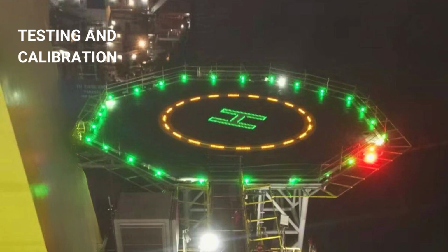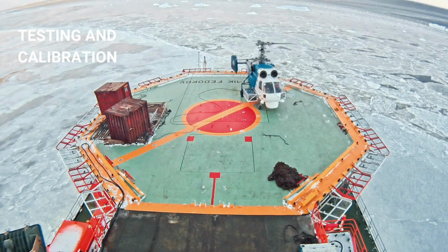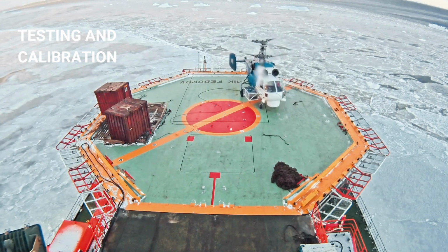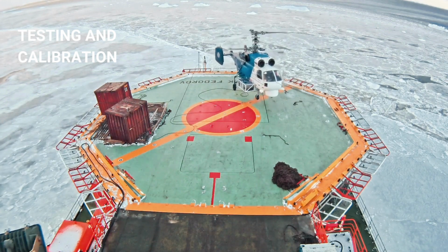With the installation complete, we proceed to testing and calibration. Lights are tested under simulated night conditions to ensure they meet ICAO standards for intensity and coverage. This involves using photometers and other instruments to measure light output and make necessary adjustments. Calibration also includes setting up automated responses to environmental changes, such as adjusting light intensity during foggy conditions. Any necessary adjustments are made to optimize performance and ensure all systems are functioning correctly.